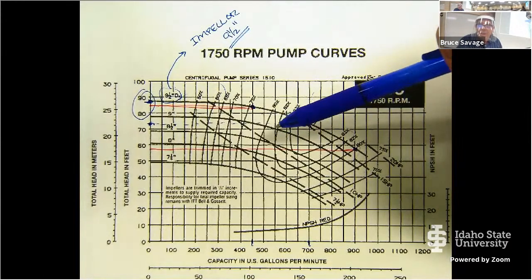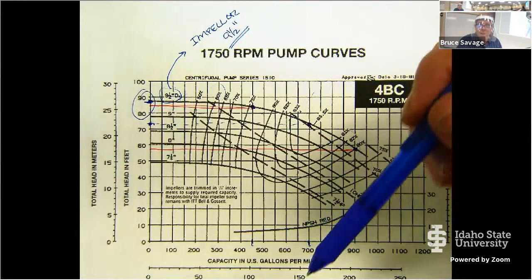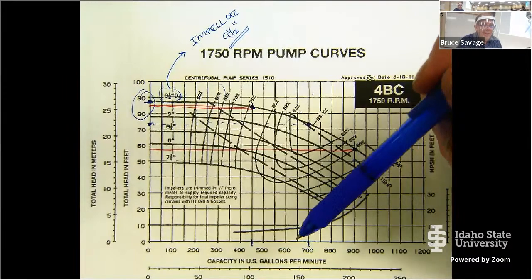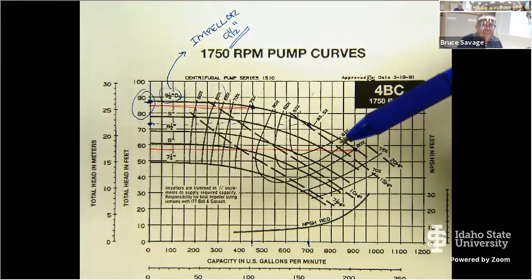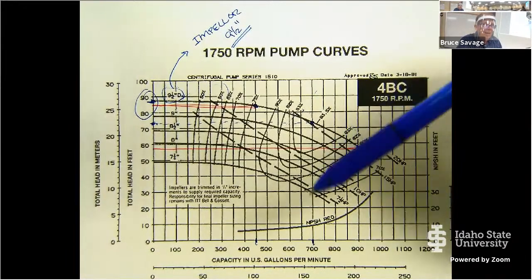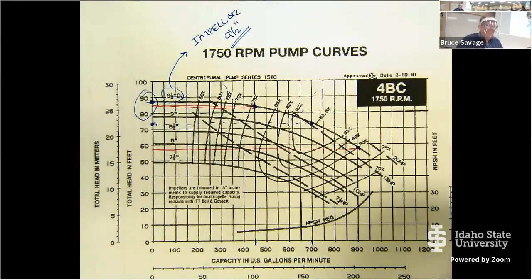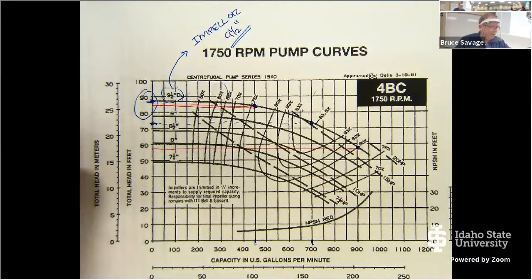Not coming down to the 85. And I looked at it and said, we can even put a pressure sustaining valve on the end of our system that'll make sure that we always get first pick of pressure. We always get high pressure, and they get leftovers, and they would still be thrilled. And the contractor, if he didn't have to put a whole new system in, a whole new pump and everything, and he could tie into ours, and they could pay our yearly fee, they'd still be happy. I pushed over the sacred cow when I approached that one. Made some people very unhappy, so I just let it drop.